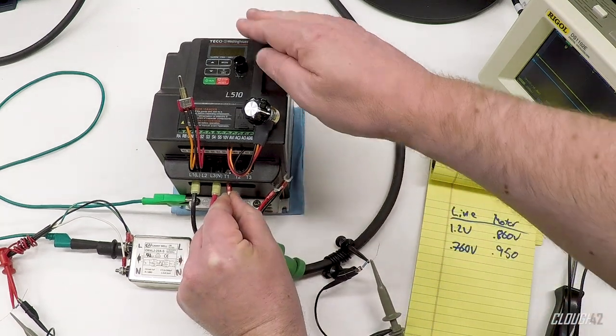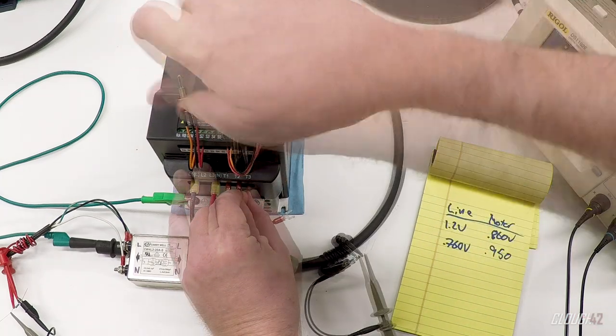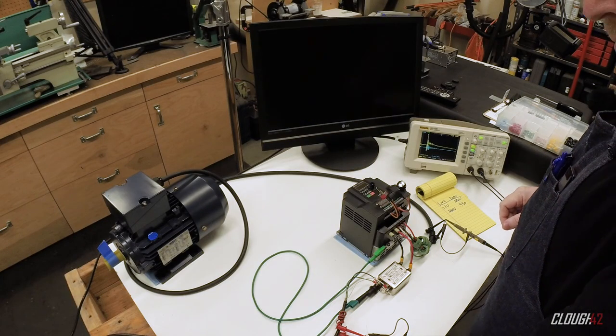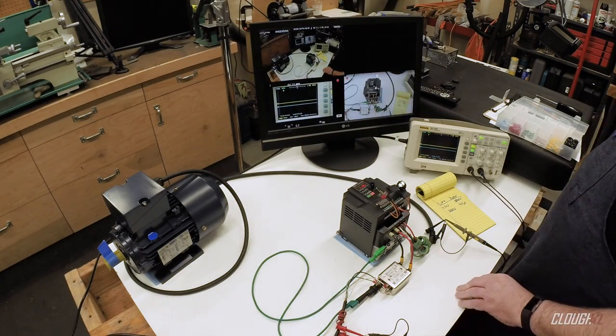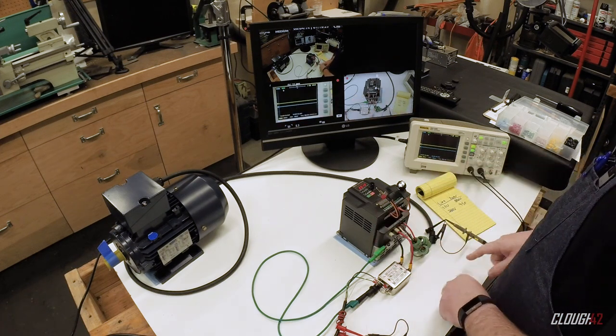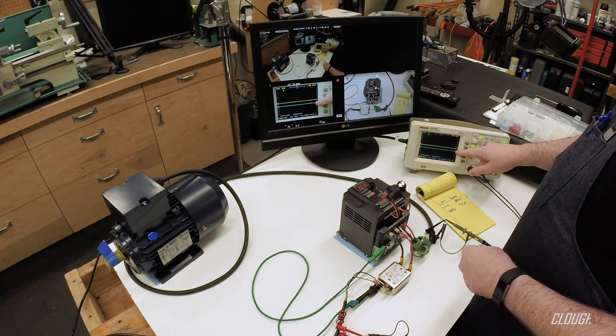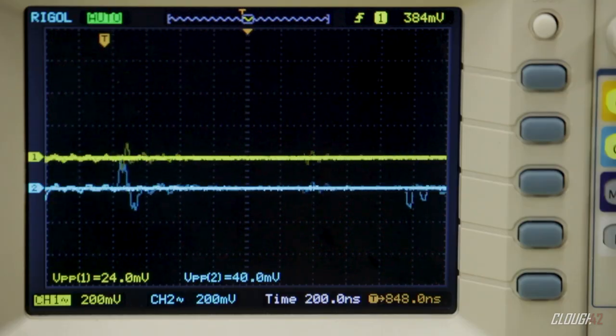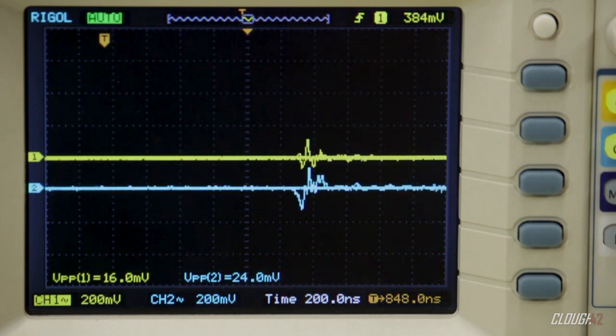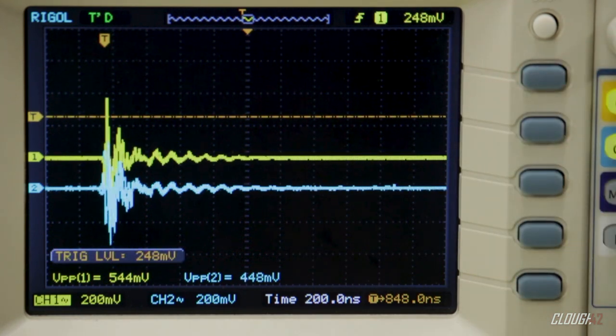And I can use zip ties to try to organize these and make them look nice, but there's my little ungodly pile of ferrites on there. Let me hook the wires back up. Okay. And plug it back in. Okay. We've got everything back up and running. Again, with the ferrites on here, let's power up the motor and see if we can see any difference on the oscilloscope. And in fact, as you can see, we're not even triggering. Wow. This has worked a lot better than I expected.